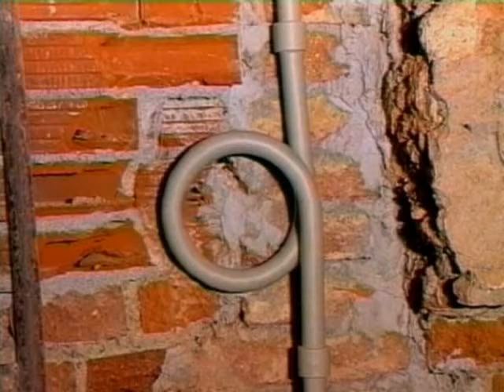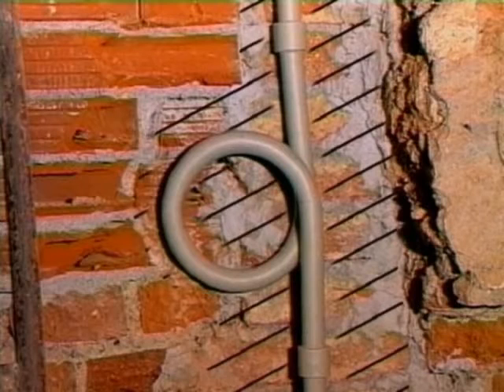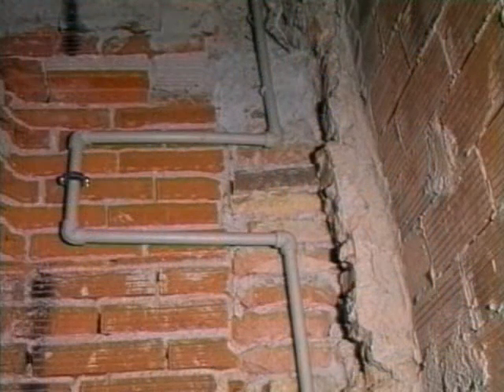If an expansion loop is used for riser pipes in a track, we must cut a pocket which we fill with flexible material in order to leave the pipe room to move after it has been covered over with cement. The same applies when using a U-shaped expansion bend.